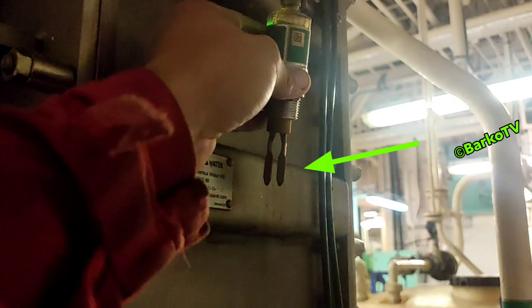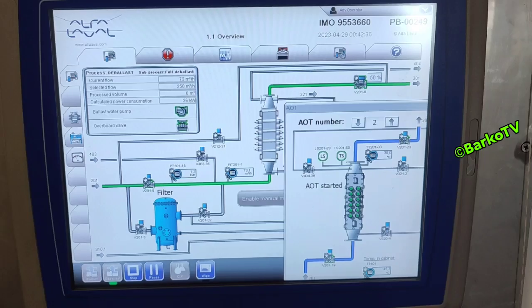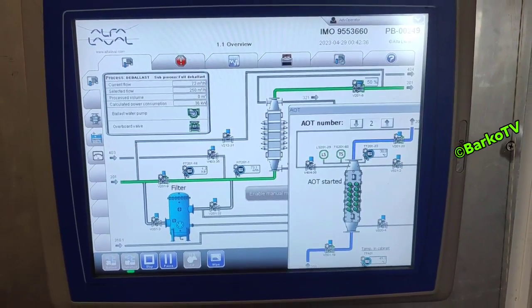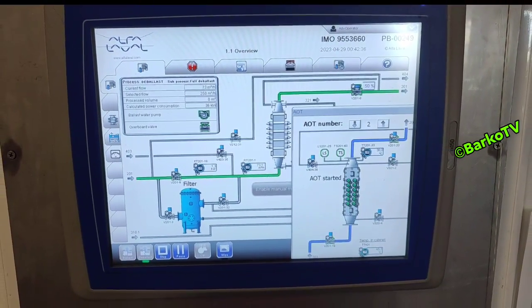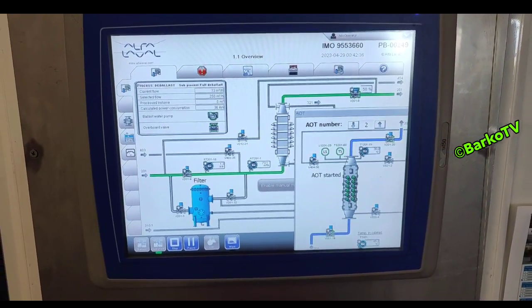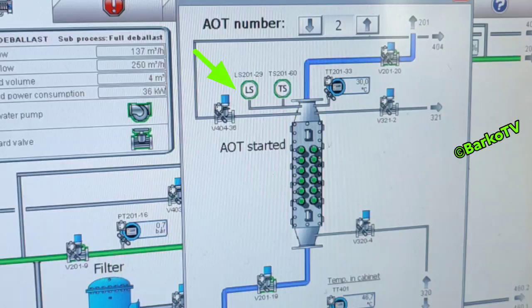This is the exciting part: the level transmitter that gave the error 'fluid level signal is missing' is actually normal. The troubleshooting I made was only cleaning the sensing point, because this sensing point is super sensitive — even one second of interruption will shut off the system. The good news is our BWTS is now running normally, as you can see the level transmitter is lit and there is flow.